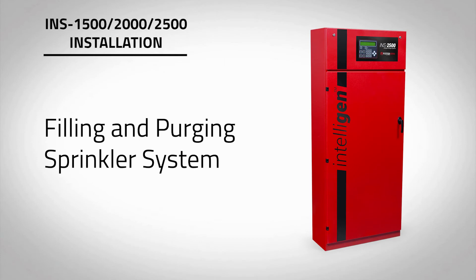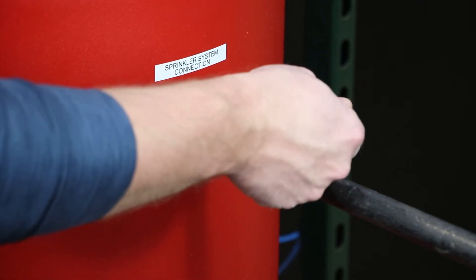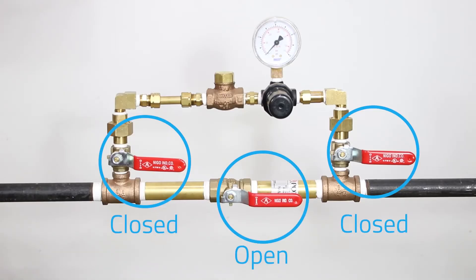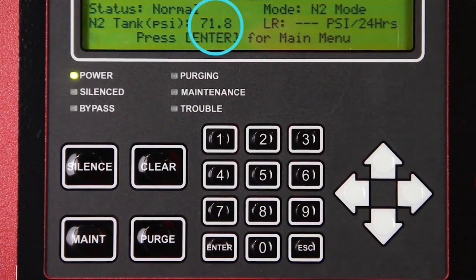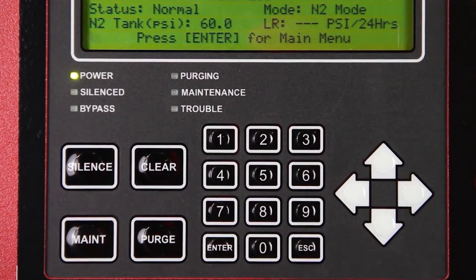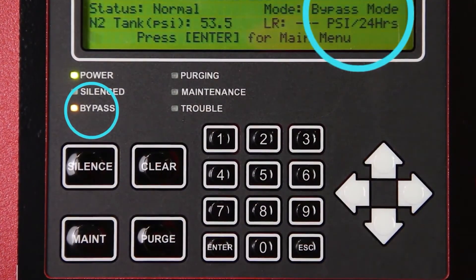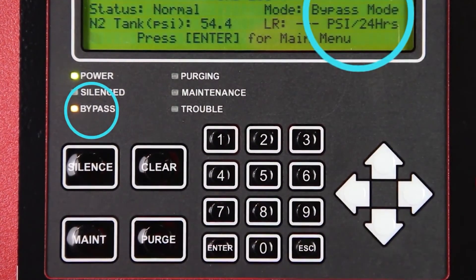Now we must fill the fire sprinkler system to supervisory pressure and begin the purge process. To fill the fire sprinkler system, open the N2 tank outlet valve labeled V03 on the nitrogen storage tank and open the bypass valve on the air maintenance device. The pressure in the nitrogen storage tank will decrease rapidly, causing the nitrogen generator to switch to bypass mode and the air compressors to turn on. The amber LED labeled Bypass will turn on and the mode on the IntelliGen display will turn to bypass mode, indicating that the nitrogen generator is filling the system with air to meet the NFPA required 30-minute fill time.